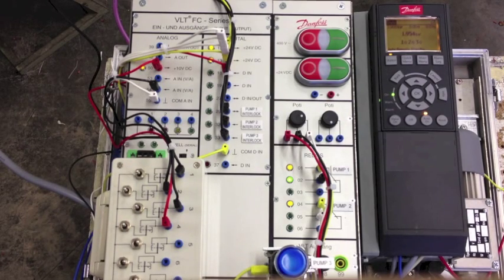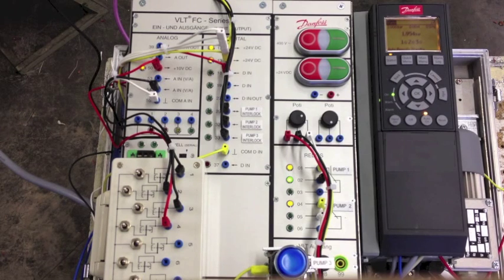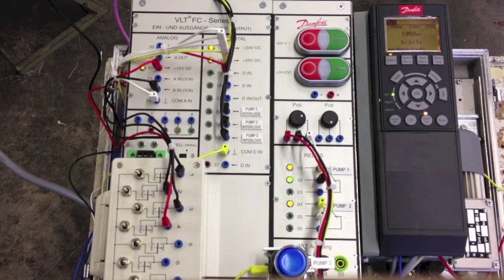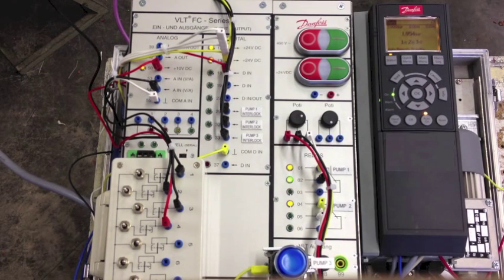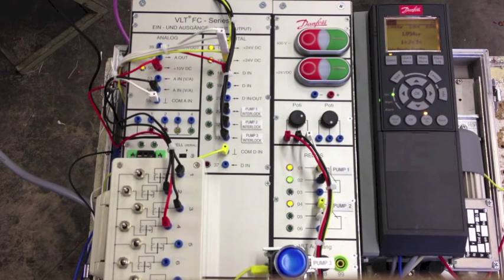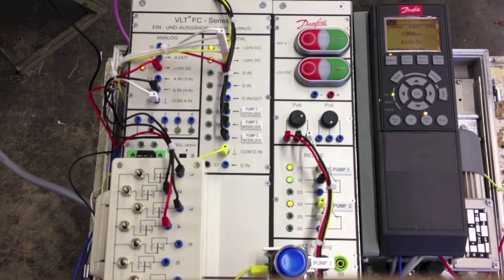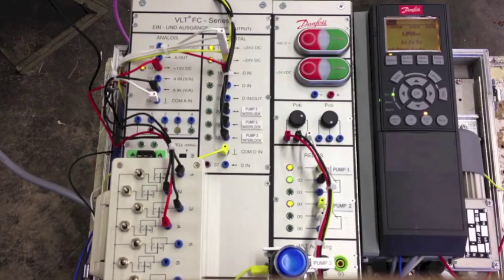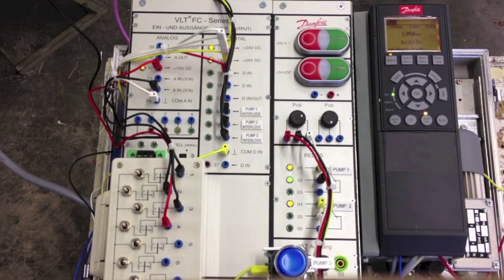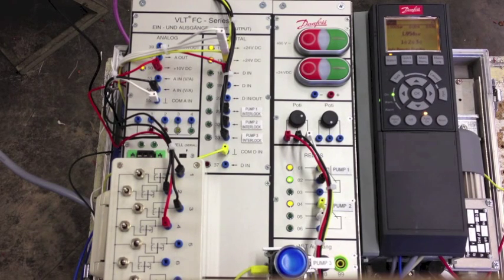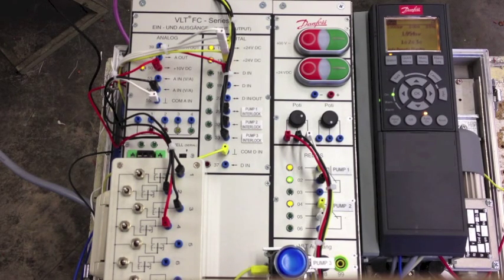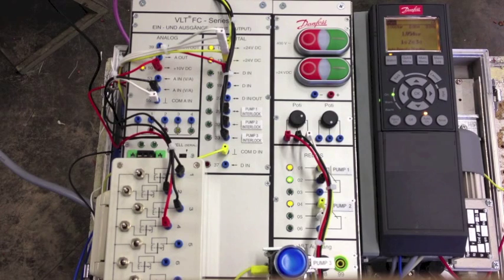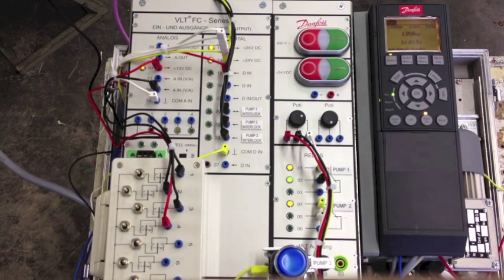Good morning! In this application we want to test the new function of the VLT AquaDrive FC202. The drive software version is the 2.03 and the new function allows to interlock also the main pump in a system composed by one drive and three pumps, using the basic cascade controller.